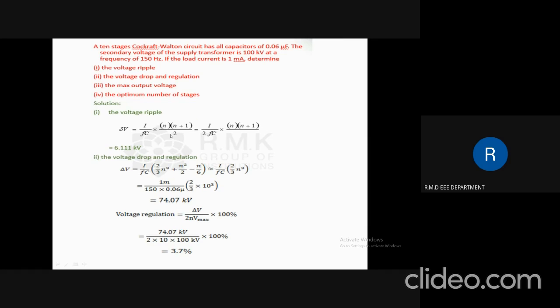We will now solve a problem related to a 10-stage Cockroft Walton circuit having a capacitance of 0.06 µF. The secondary voltage of the supply transformer is 100 kV at a frequency of 150 Hz. If the load current is 1 mA, we have to determine the voltage ripple, voltage drop and regulation, the maximum output voltage, and the optimum number of stages. The voltage ripple is given by delta V = (I / FC) × N(N+1)/2. Substituting I = 1 mA, F = 150 Hz, C = 0.06 µF, and N = 10, we obtain a ripple value of 6.1 kV.